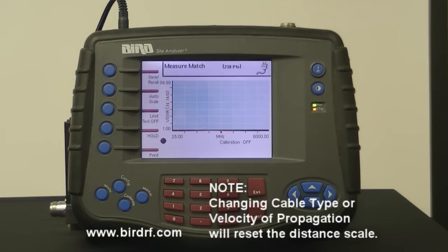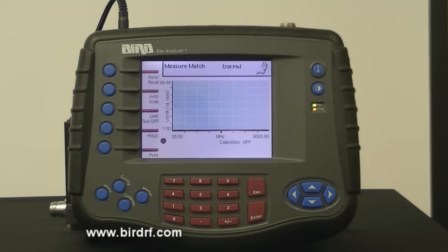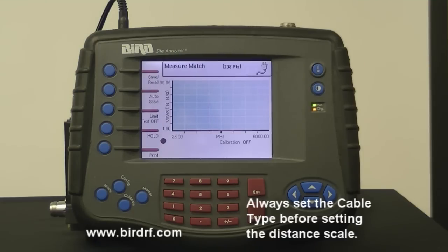Keep in mind, changing the cable type or the velocity of propagation will reset the distance scale to the maximum possible distance. Therefore, always set the cable type before setting the distance scale.